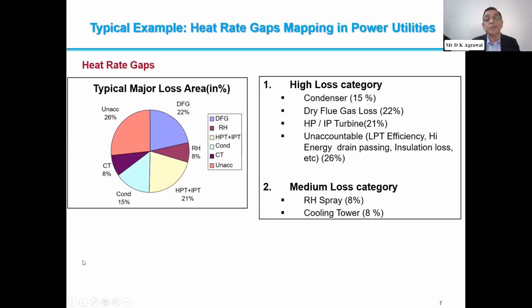Well, here are the type of exercises which have been done in the past. There are certain figures which we find as typical deviations. You can see condenser having losses of the order of 15%, dry flue gas losses 22% because of many reasons. The air heaters may not be in a good condition, or seal leakages and all, and HP, IP turbine. In many places the turbine efficiency degradation goes unnoticed, or some methods adopted for measurements are not properly followed. So we sometimes are not getting exact information.